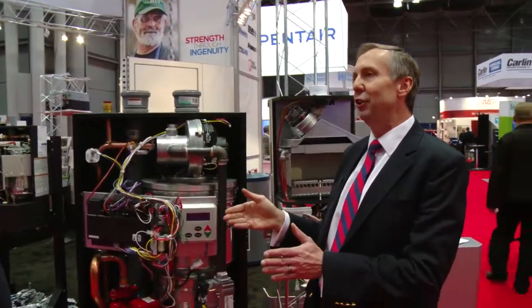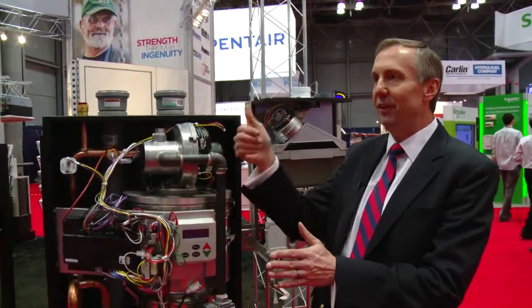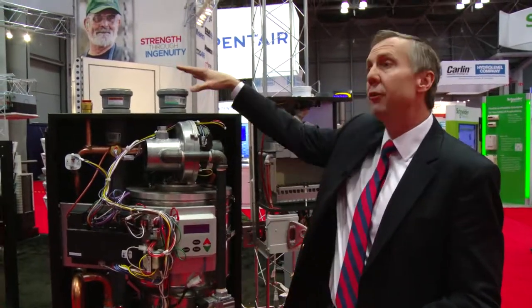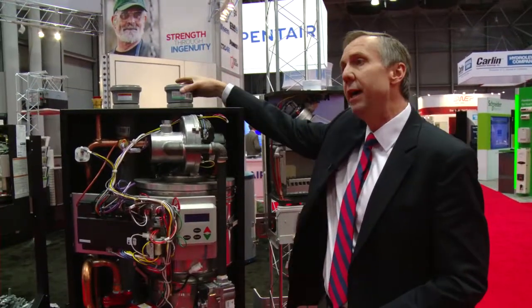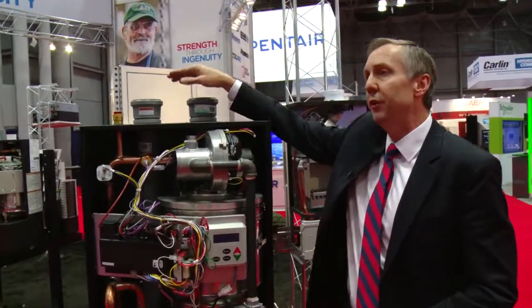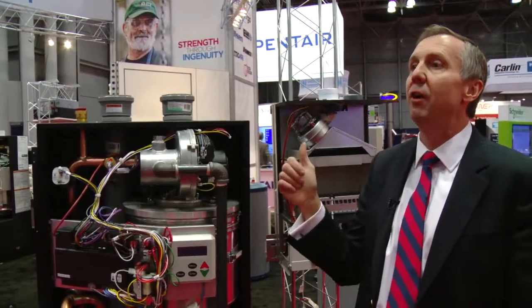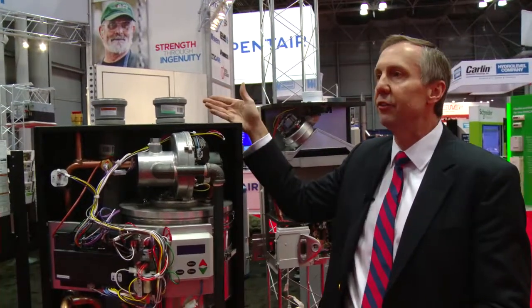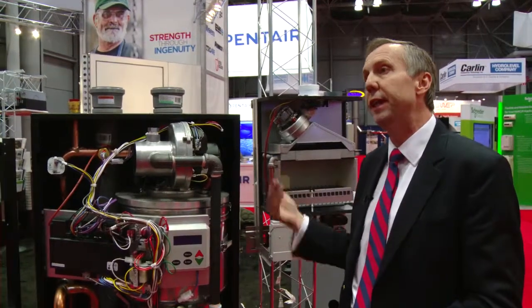It's not like you're going to want to go... We try to keep the pressures equal, i.e. I wouldn't want to have a vent that's 80 feet long with a very short intake assembly. Gotcha. Then you could run into some potential problems. The other nice thing about this that we recently did, back to the cascading, is you can actually combine these vent systems now. Okay. And in the IOM, there is a connector that's put on the discharge side. It's a check valve. Sure. That check valve would allow you to now only have to have one vent going out the side. You would still need multiple vents coming into the inlet side. But that's very nice when you're starting to do larger properties where you need to cascade these boilers.